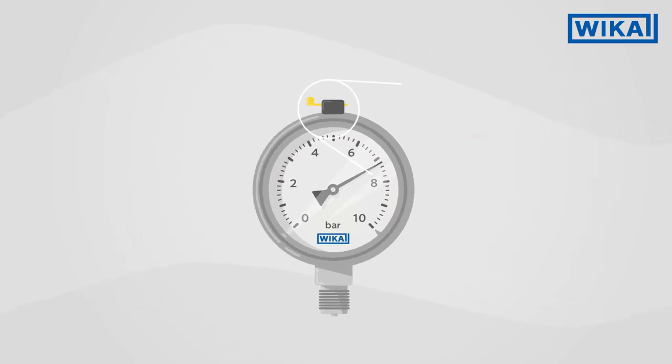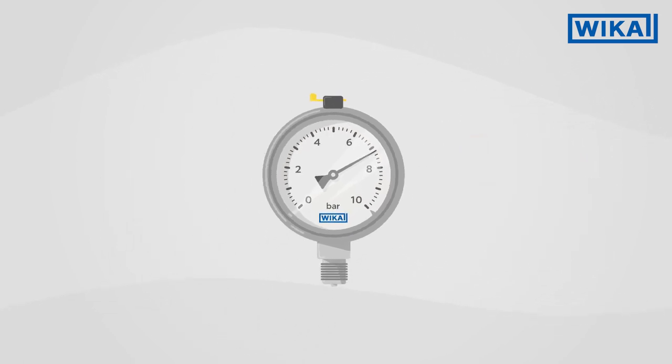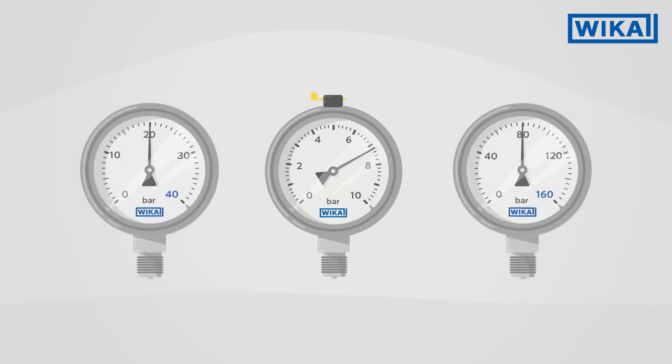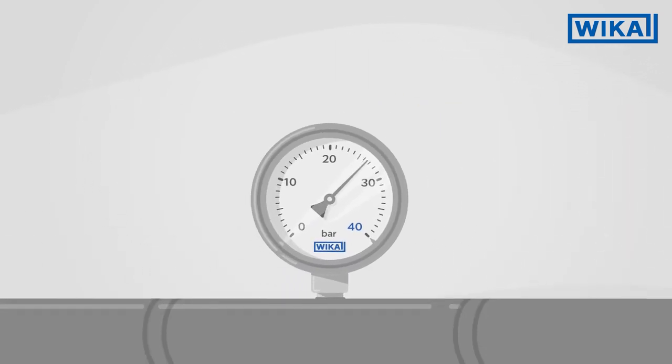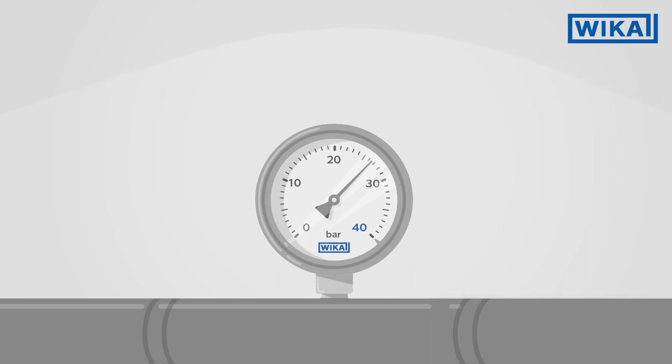However, not all WIKA pressure gauges have such a vent valve with this yellow lever. It is not needed for pressure gauges with pressure ranges over 16 bar.